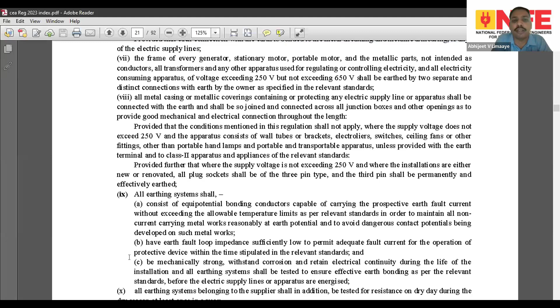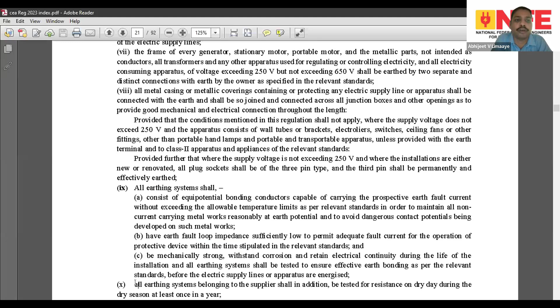Just to take an example, if we do a fault loop impedance measurement, we arrive at a value of, let's say, 5 ohm, and we are looking at the system to trip at a single phase earth fault. So we should have a setting which is less than 46 ampere, because that would be the kind of fault current we'll be getting. Just because there is a provision for fault loop impedance and you measure a fault loop impedance, things don't stop at that. You have to make sure your settings are there to ensure automatic disconnection within the stipulated time.